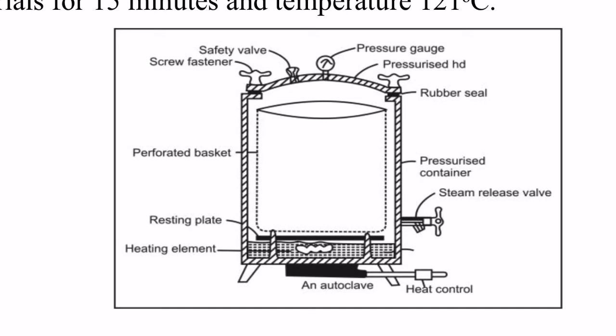Approximately six to eight screws are placed all around the lid. Safety valve, pressure gauge, and pressure indicator are present here. The safety valve works just like a pressure cooker whistle — if the pressure becomes too high, it releases the pressure. The pressure gauge records and shows how much pressure is generated. Under the lid there is a perforated basket attached, and at the bottom of the autoclave there is a heating element.